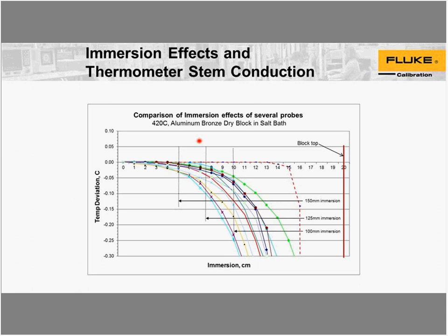Well, what we try and do is compensate for that by using different heating element values throughout that block, equalize that out so it's as flat as possible. Well, that's something you can do in an approximate sense. So I built a block that was immersed into a salt bath, and you can imagine the salt bath was pretty uniform.